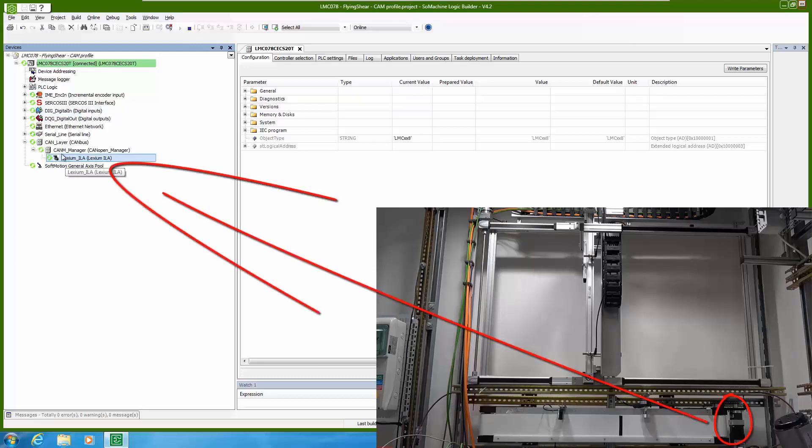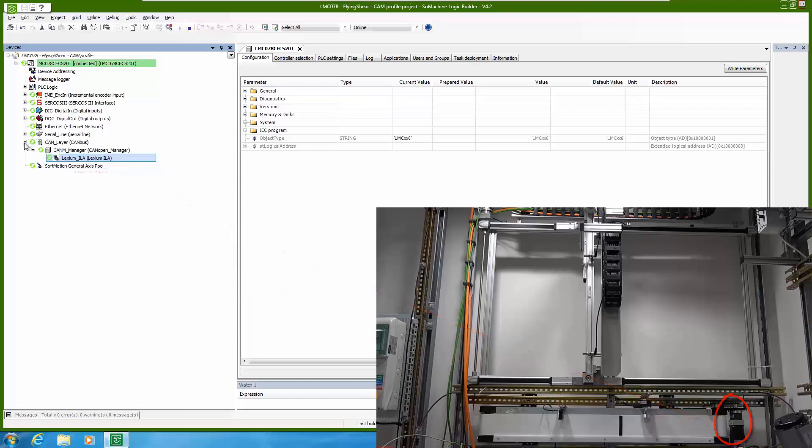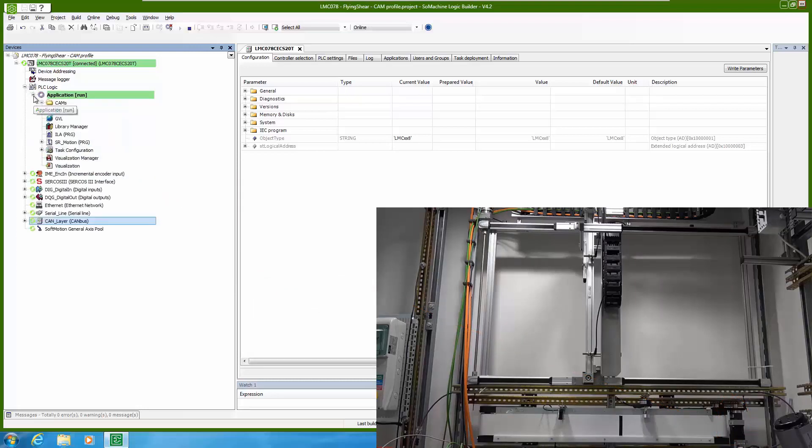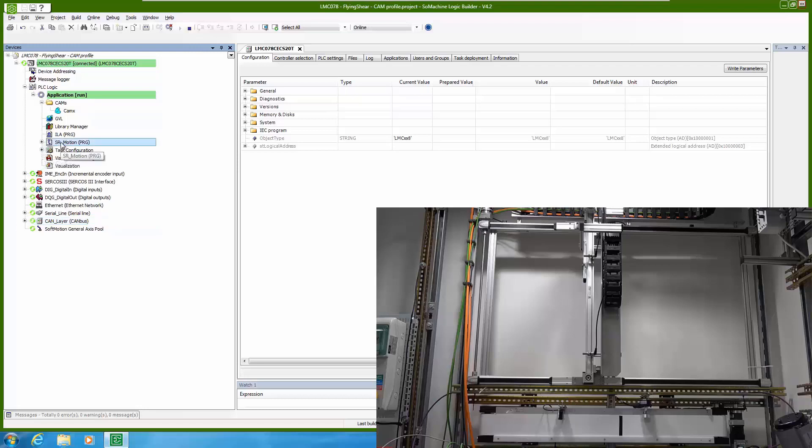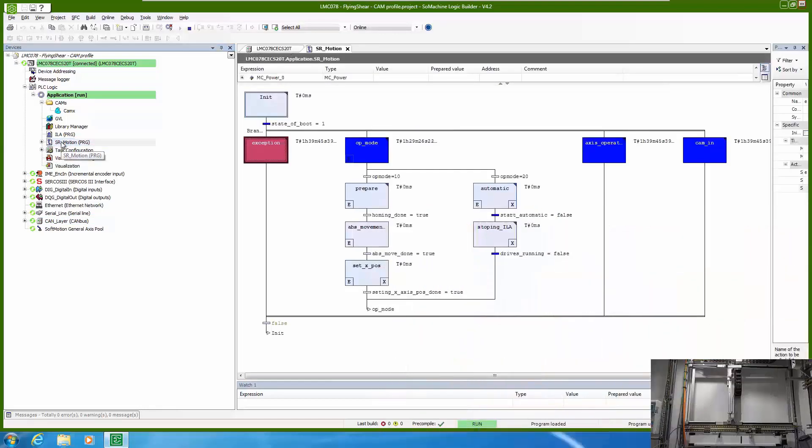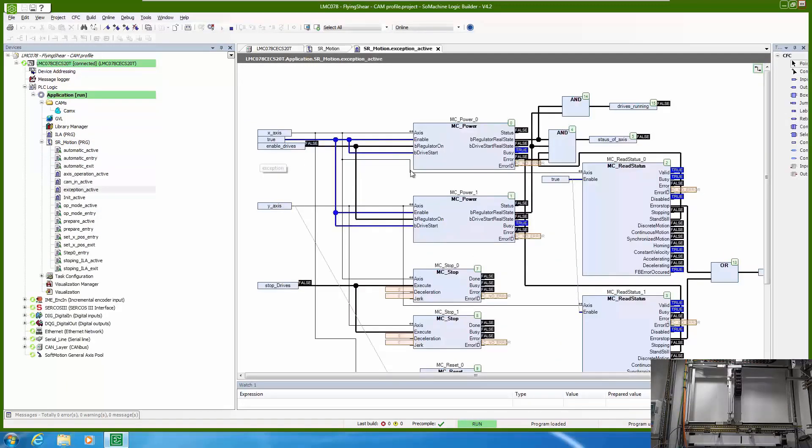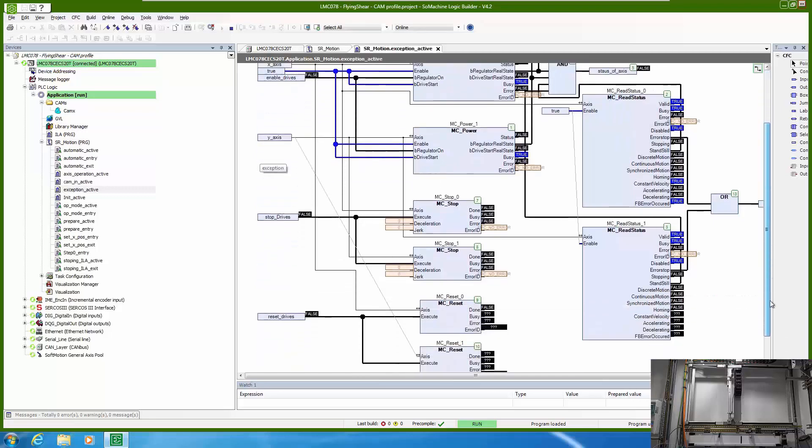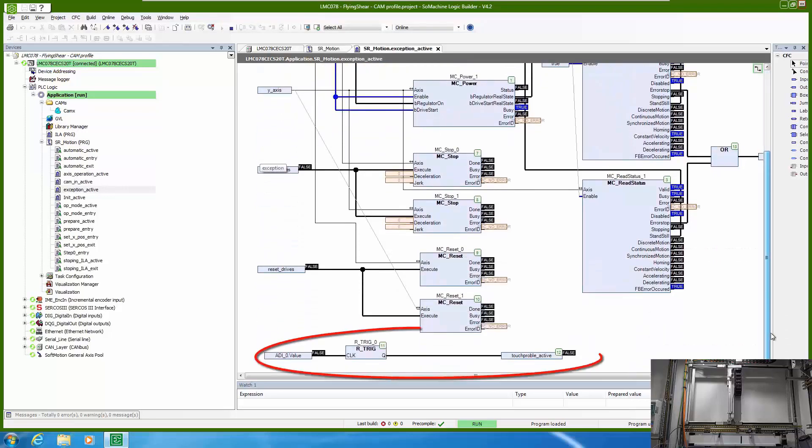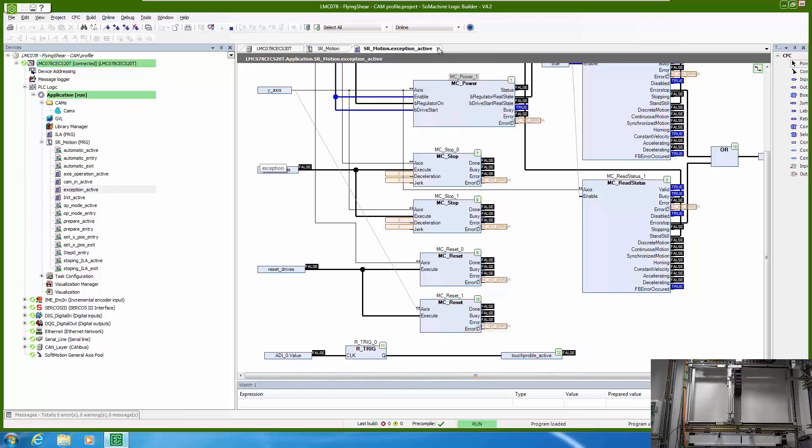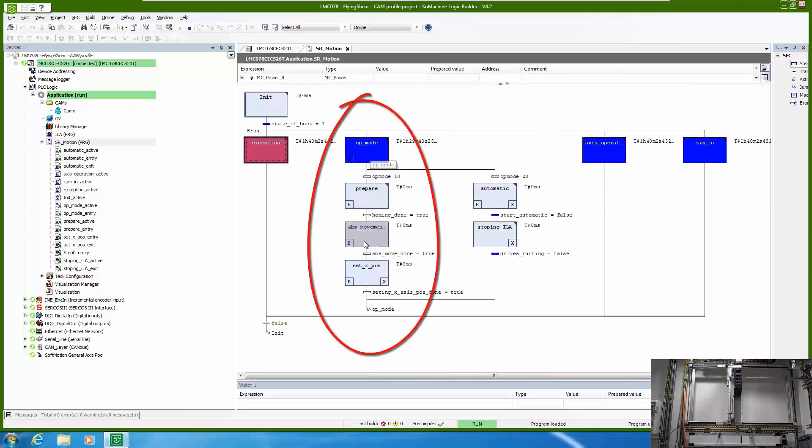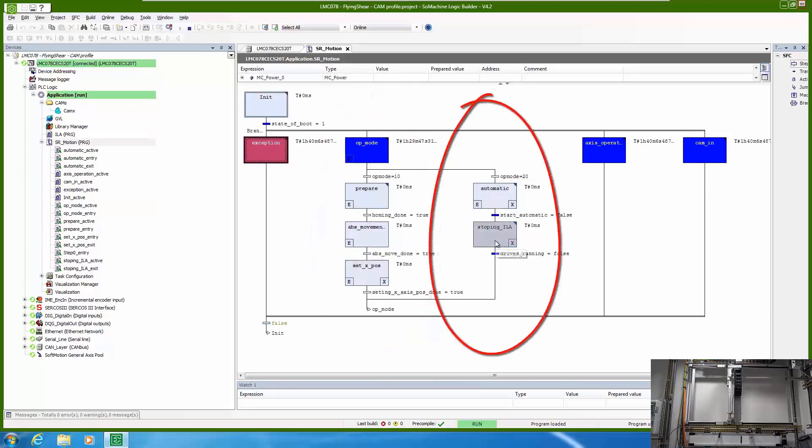Now let's see a bit of our actual application. If we open our application we will see that it's separated in four parts. In first part we are just running a drive, reading a status and most important checking our touch probe input. In second part we have operating modes and we have two. One is preparing the axis so homing, moving to position and then automatic to run our cam profile.